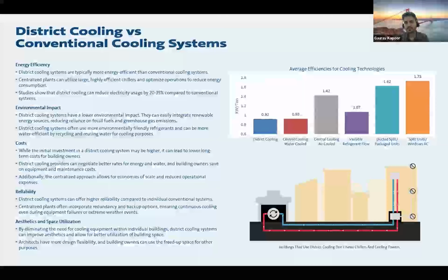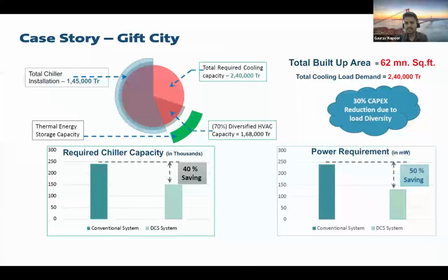Now, how DCS has actually worked out. So this is the Gift City. It's a screenshot which was available with me from a presentation from Gift City. If you look at the Gift City in Gujarat, the total required cooling capacity is 240,000 tons for a total built up area of 62 million square feet. But with the help of DCS, with a 70% diversification, they needed only 168,000 tons of refrigeration, of which they only installed 145,000 tons of chillers, and the rest of the diversified load is being handled with the help of thermal energy storage.